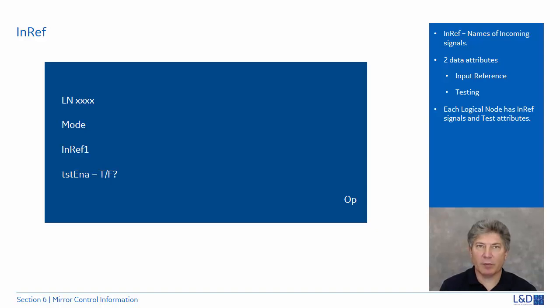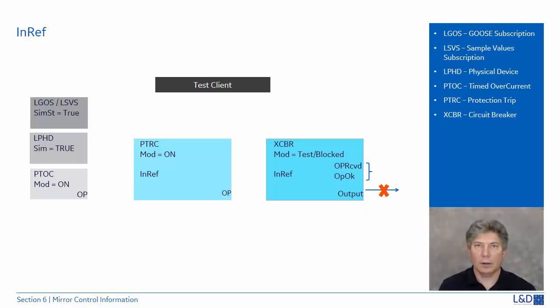So to provide an example, we have a logical node with a PTOC. We've got a mode that's set to on. The in reference signal is the phase A current. And the testing portion is the test enable, which is set to false in this example. Let's review the testing that's associated with the in-ref signals. Once again, the idea here is to be able to test the system without influence of the process.